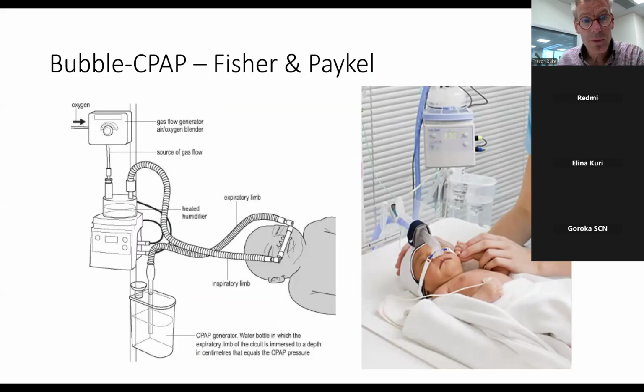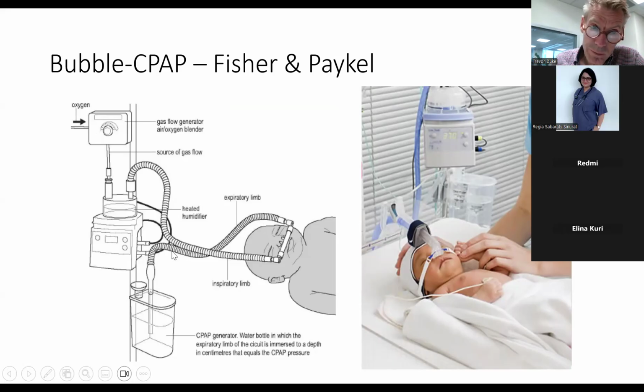So it has a source of gas flow here. It has a source of oxygen; it's a blended source of oxygen, so you still have to have an oxygen cylinder to generate some oxygen through the machine. It's got a heated humidifier here. And then it's got an inspiratory limb and an expiratory limb going from the patient, and that goes to a tubing that goes underneath the water in this bottle. If the tubing is 3 centimeters under the water, then it's 3 centimeters of CPAP. If it's 7 centimeters under the water, then it's 7 centimeters of CPAP. And you can adjust the tubing up and down depending on the CPAP you're giving. That's the Fisher and Paykel machine.